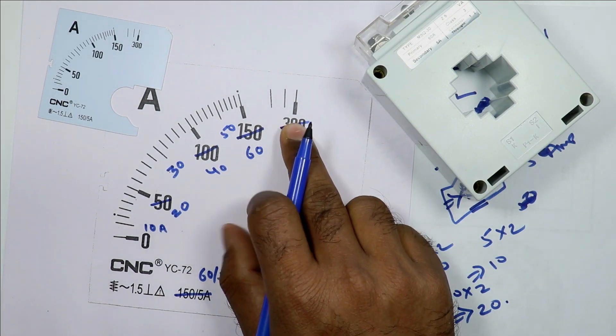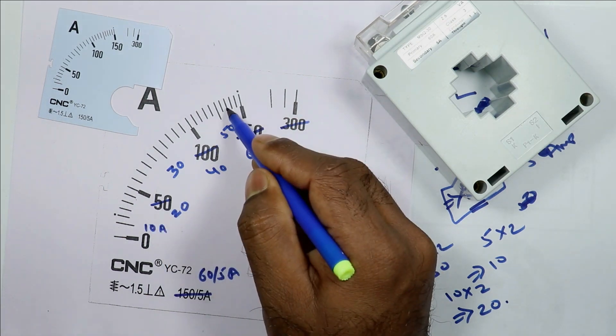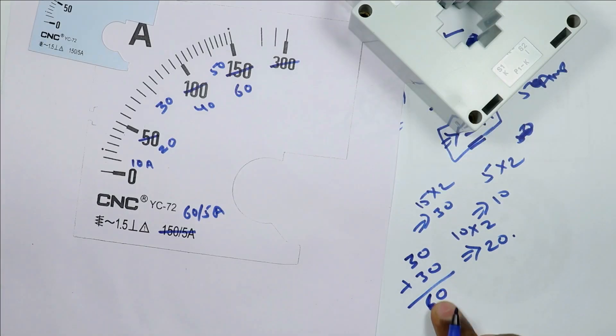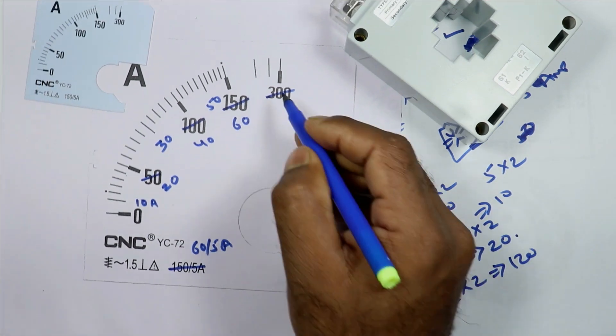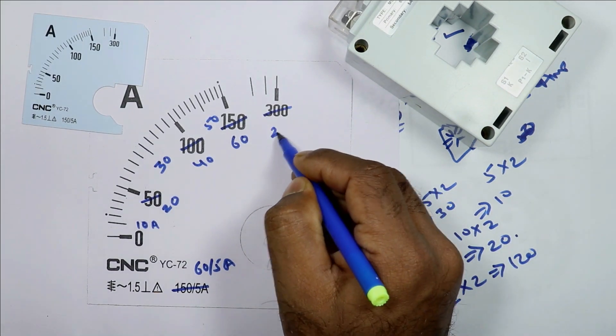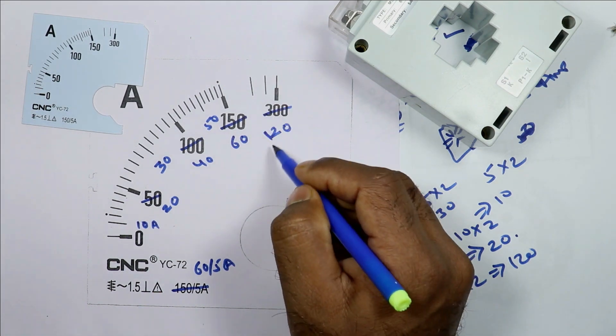For this, you have to count how many lines are there in between. Till here counting was 30. From here to here, 30 more will be added. So 30 plus 30 is 60. And if multiplied by 2, answer is 120. In place of 300, 120 ampere must be written. If ammeter shows reading till here, this means 120 ampere current is flowing.